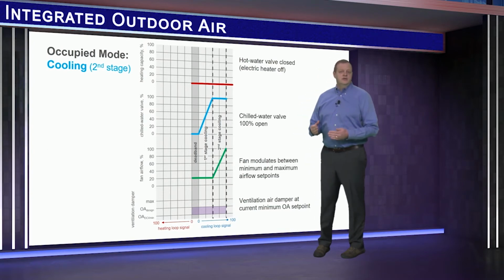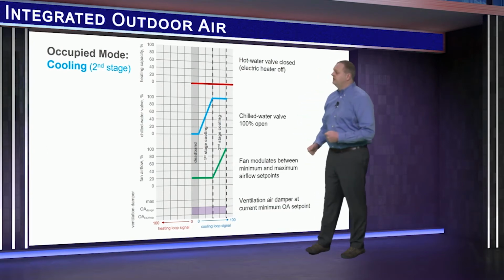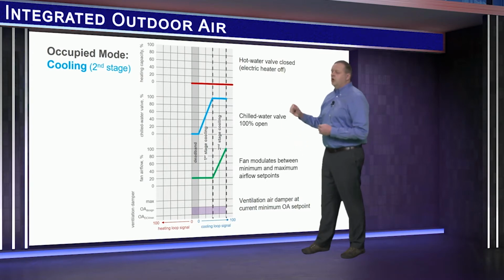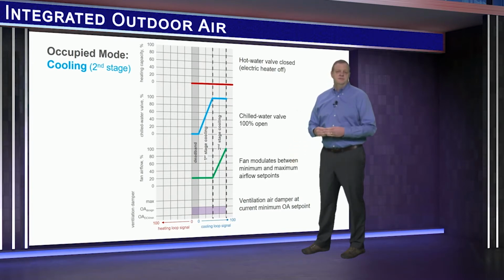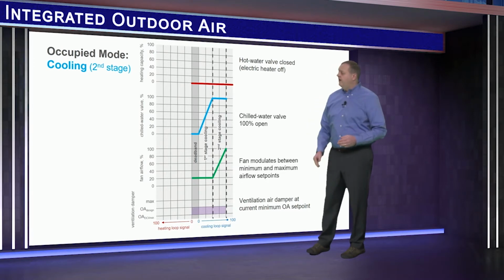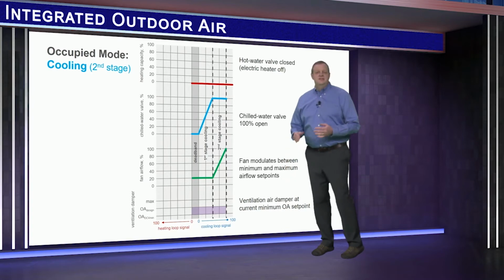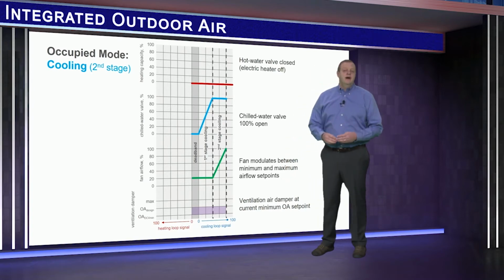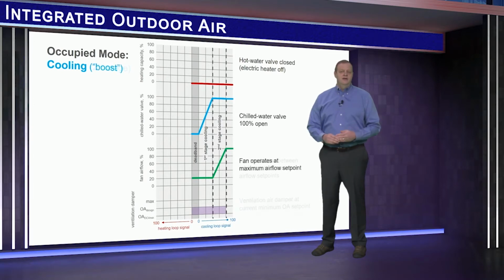When the requested cooling capacity has increased to the point where the chilled water valve has opened to 100%, the controller then begins to increase the fan speed, while this chilled water valve remains at 100% wide open. This is the second stage of cooling. Now so far, the ventilation damper is still being controlled to the minimum outdoor airflow set point. So it's bringing in only as much outdoor air as needed for ventilation.